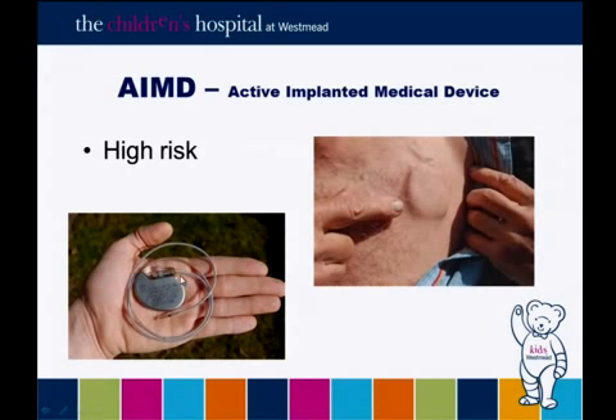They'll go for 10 years, so if you've got battery technology that stimulates your heart for 10 years inside you, along with all the computing and all the radio receiving stuff that you need to program it, there's a lot to these little fellas to keep them going for 10 years. There's not much that you can switch on and it goes for 10 years, let alone keeps you alive for 10 years, all right? So you can see why it's such high risk. They usually implant them under the chest, so they're totally implanted. If you want to communicate with the device, you need an RF coil that's specially tuned, and very sophisticated programmers to change all sorts of characteristics in the pacemaker to make it do what you want.